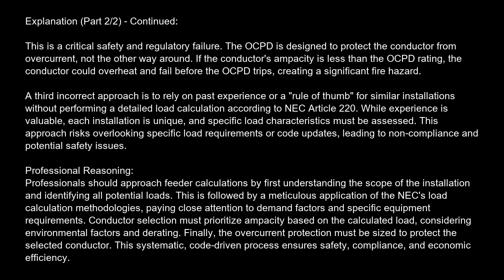Professional reasoning. Professionals should approach feeder calculations by first understanding the scope of the installation and identifying all potential loads. This is followed by a meticulous application of the NEC's load calculation methodologies, paying close attention to demand factors and specific equipment requirements. Conductor selection must prioritize ampacity based on the calculated load, considering environmental factors and derating. Finally, the overcurrent protection must be sized to protect the selected conductor. This systematic, code-driven process ensures safety, compliance, and economic efficiency.